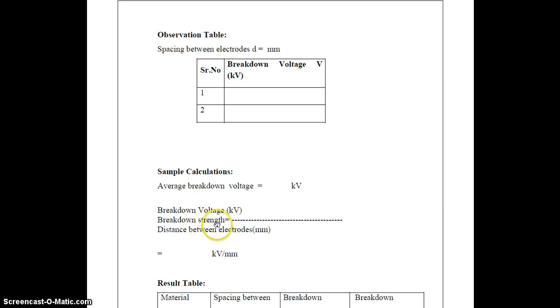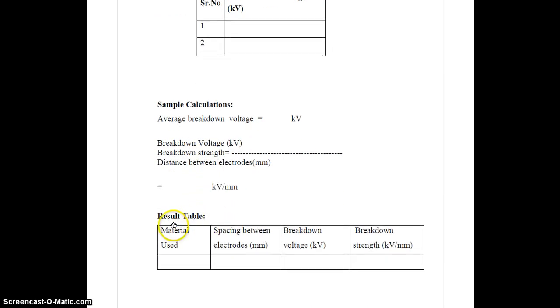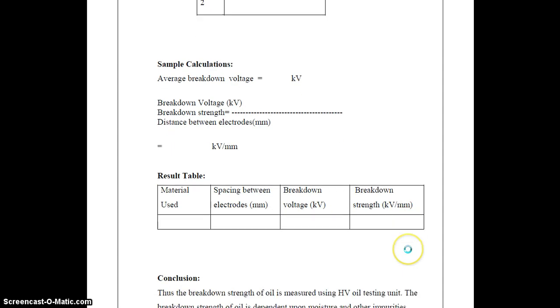Breakdown strength is the ratio of breakdown voltage to the distance between the two electrodes. The unit of breakdown strength is kilovolt per mm. The result table shows which type of material is used, the spacing between the two electrodes D in mm, then breakdown voltage in kilovolt and breakdown strength in kilovolt per mm.